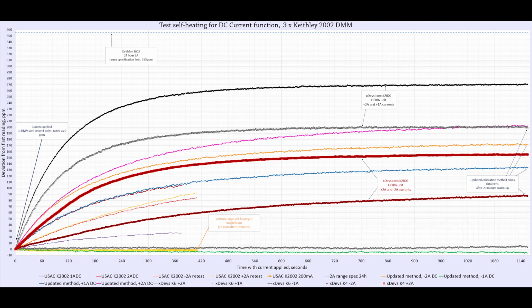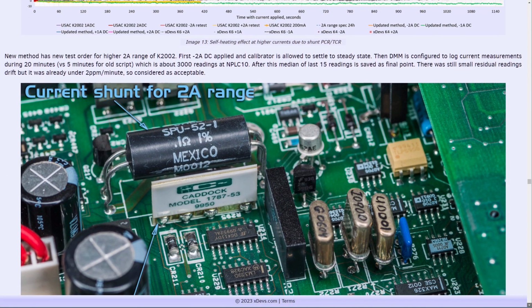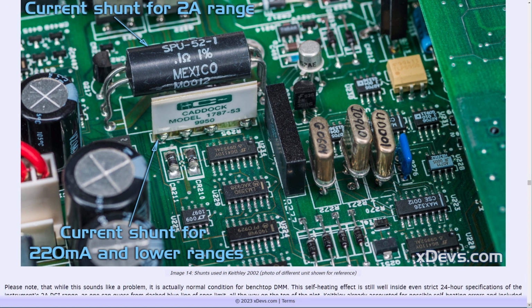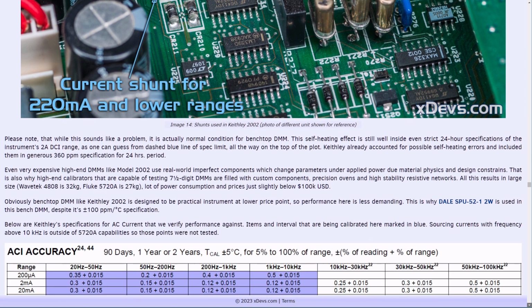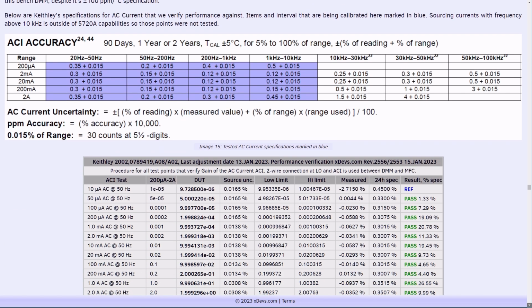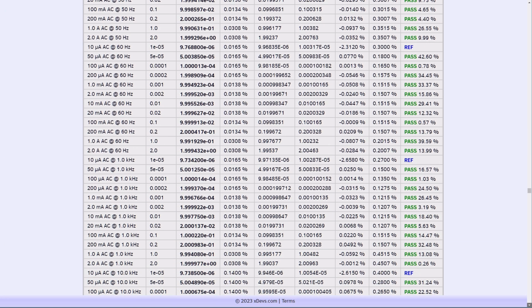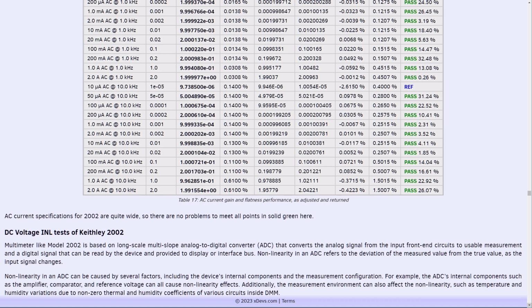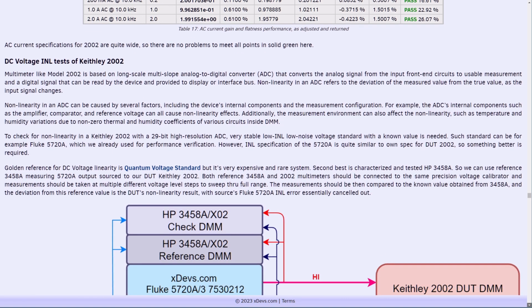of the current shunt in model 2002. I've tested both of my own Keithley 2002s to verify this behavior, and it is indeed very similar. So calibration procedure for the 2 amp range was improved as a result, allowing additional 20 minutes for DMM shunt to reach stable condition. We don't have this problem for AC current, so at this point we have completed adjustment and calibration of Keithley 2002.